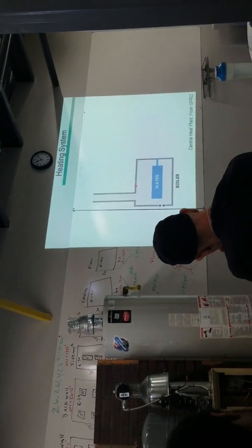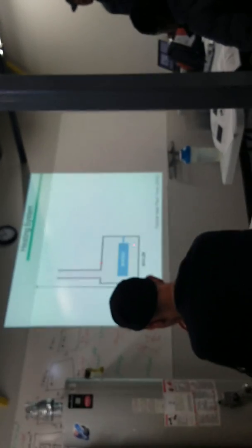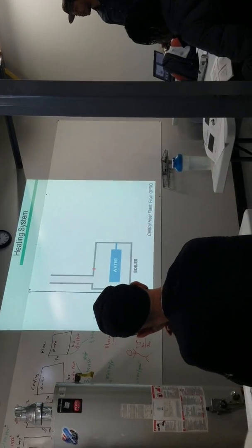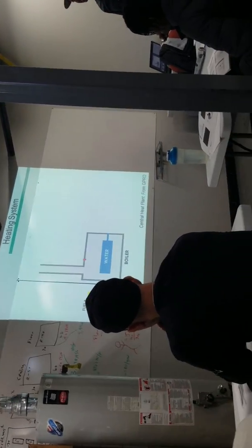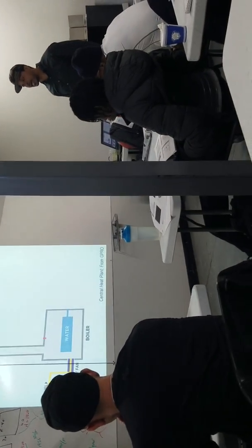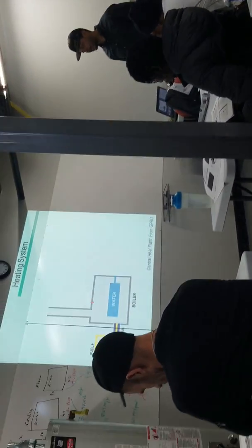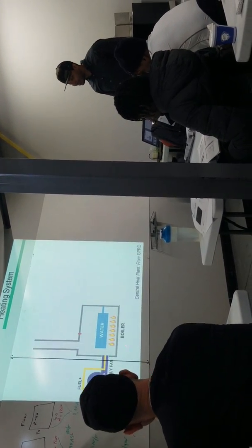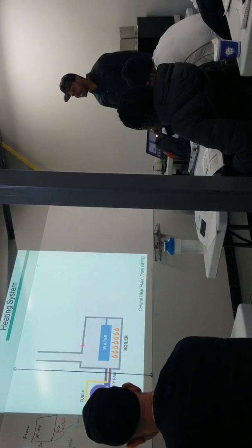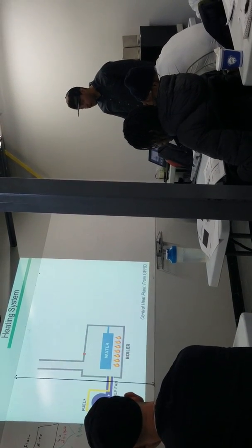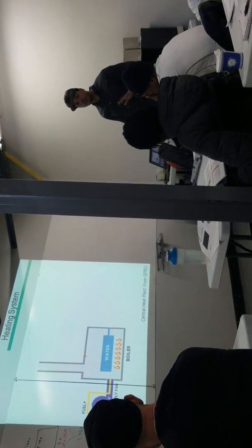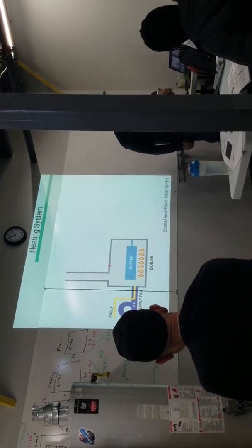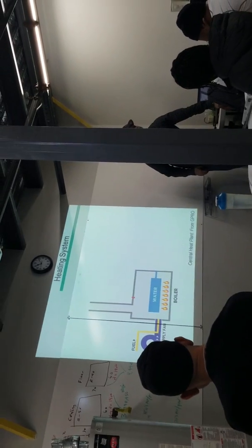Right, in this case we have a cast iron sectional boiler. Inside there's going to be water, right? So this is going to be most likely, external burner tells me that it's oil, right? If you see the fan, that's for combustion air. This doesn't really do justice, but this can technically be a dual fuel system, right? You got oil here, you got gas down there. The thing about dual fuel, why it's important, is because, I think I explained this to y'all before, at certain times of the year, it's cheaper to use oil than it is to use gas.